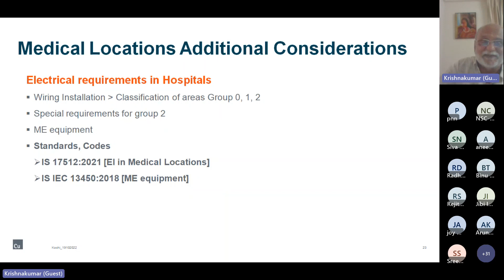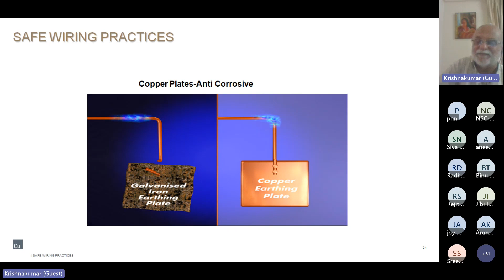Another thing people ignore most in house wiring is the earthing. In an industrial situation the scene is different. The industrial engineers are trained, and whenever they get some electrical installation done, they ensure that earthing is done properly, and they measure the values. But unfortunately, in the case of buildings or house wiring, it is left to the imagination of the electrical contractor or a wireman. I have seen some cases where they put bare copper earth wire, run it all around, and then terminate it on a GI plate. Again, it is all in the name of saving money for the customer. Unfortunately, he is put to trouble.